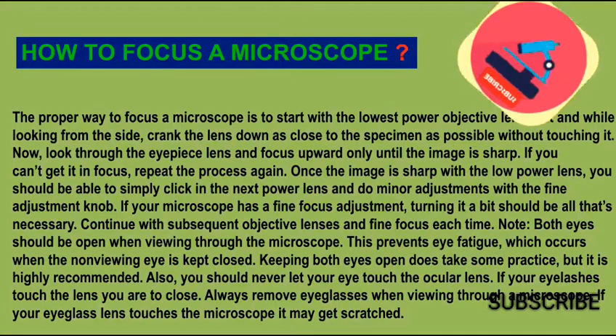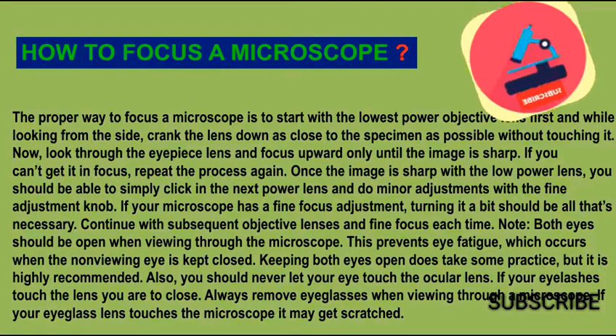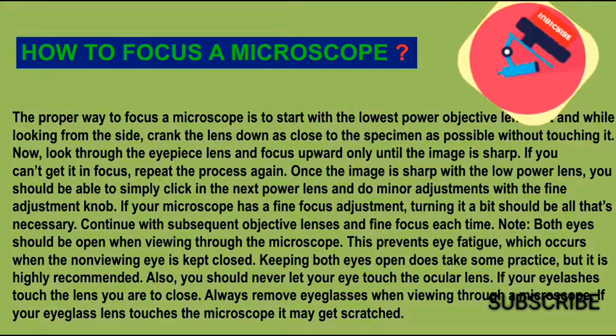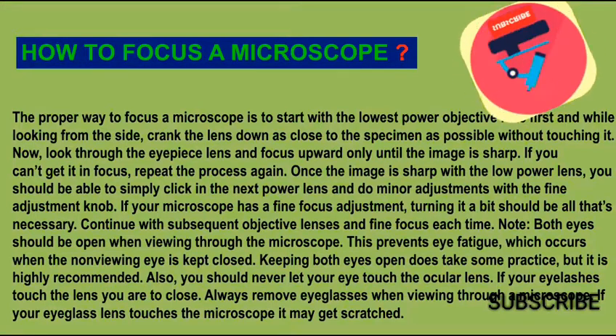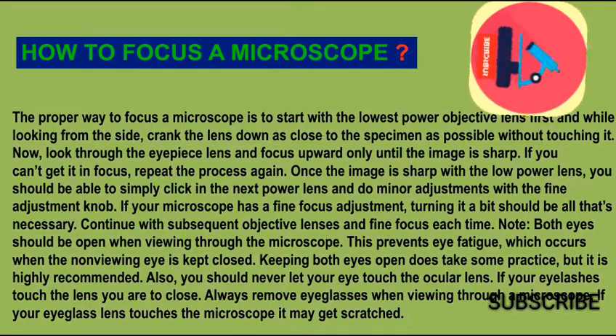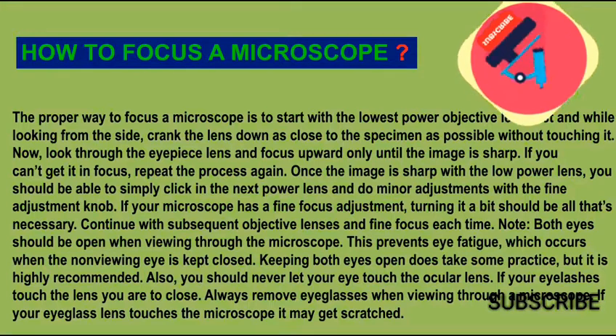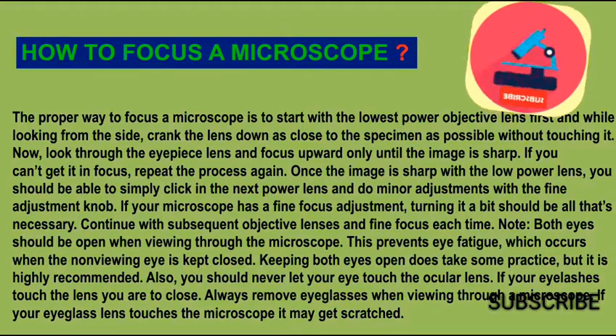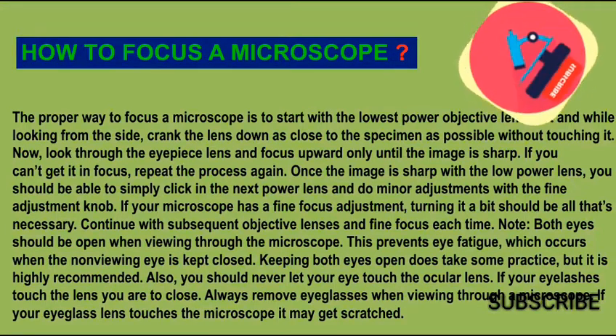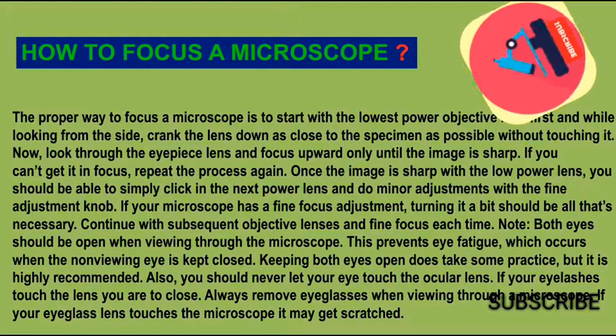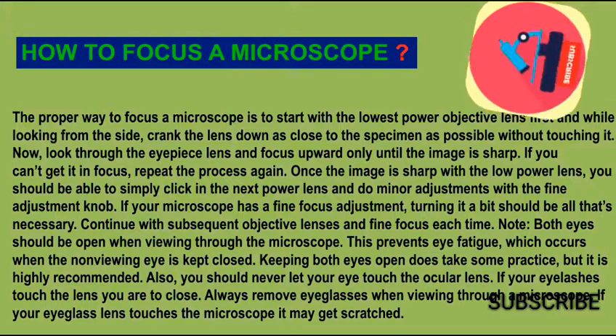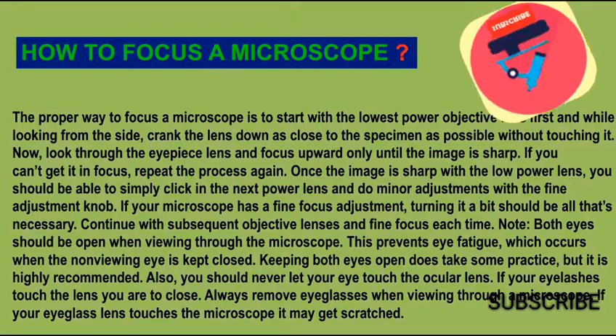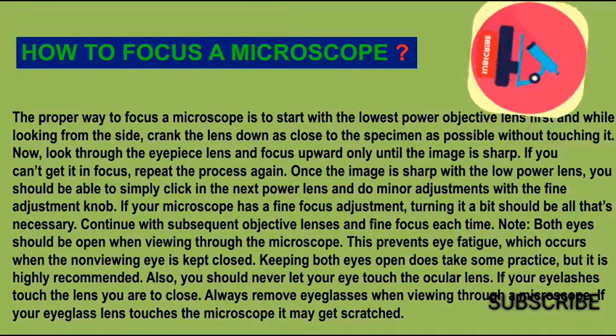To focus the microscope properly, start with the lowest power objective lens first. While looking from the side, crank the lens down as close to the specimen as possible without touching it. Then look through the eyepiece lens and focus upward only until the image is sharp. If you can't get it in focus, repeat the process. Once the image is sharp with the low power lens, simply click in the next power lens and make minor adjustments with the fine adjustment knob. Continue with subsequent objective lenses and fine focus each time.